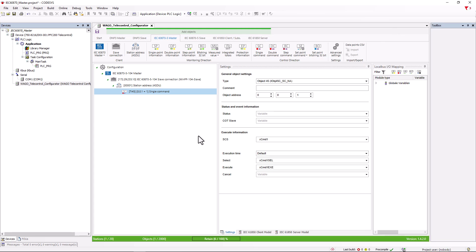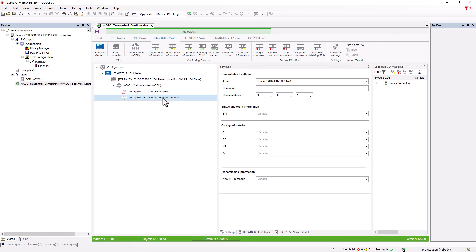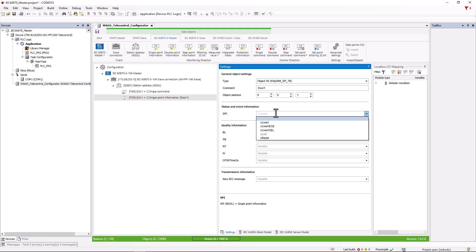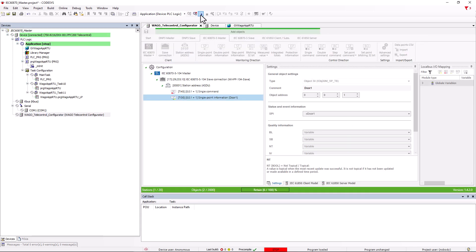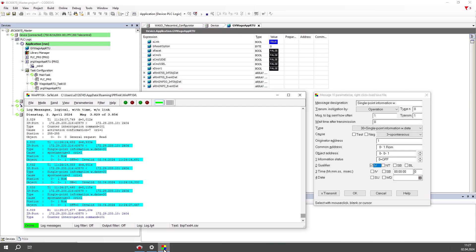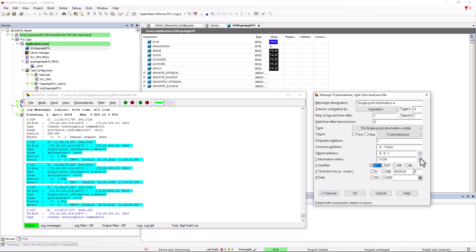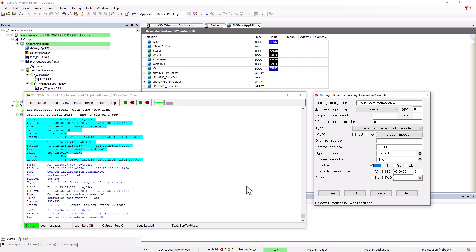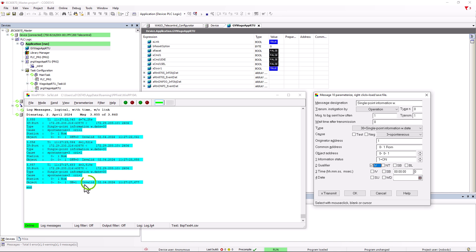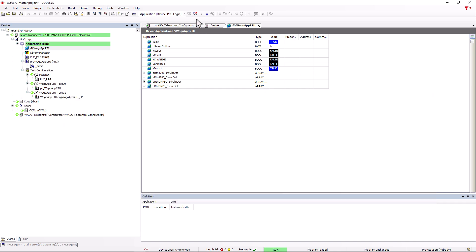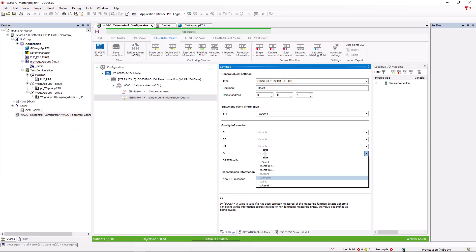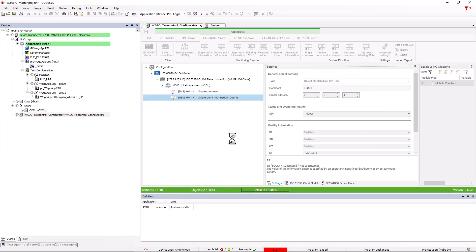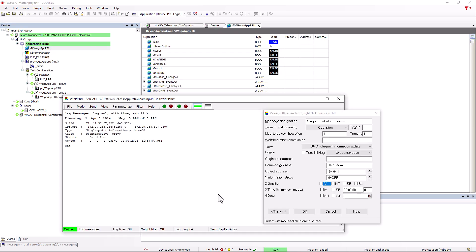If we look at the individual message, we again have the general settings with type, comment and object address in the top field. Below this is the field for the actual message. Here we create a bool variable. We now use WinPP to simulate a slave and send a spontaneous message from it that DoorContact1 has been triggered and the variable in the master changes to true. In the telegram, we see that the IV bit is set. To be able to analyze this in the master, we create a variable for the IV bit in the quality information area.